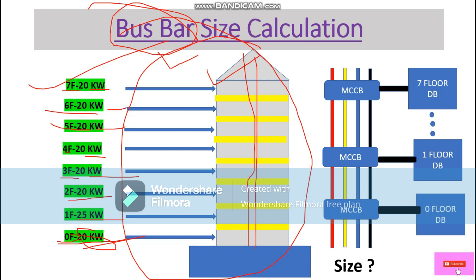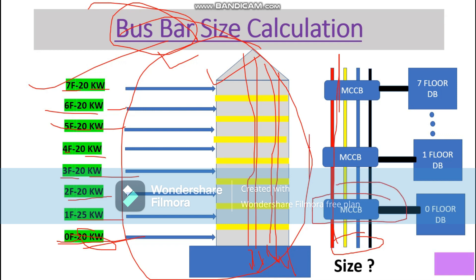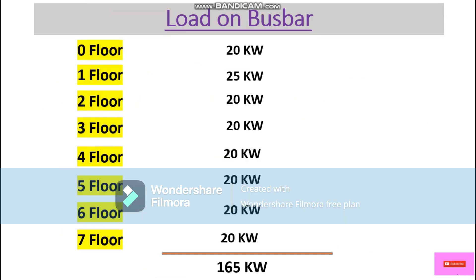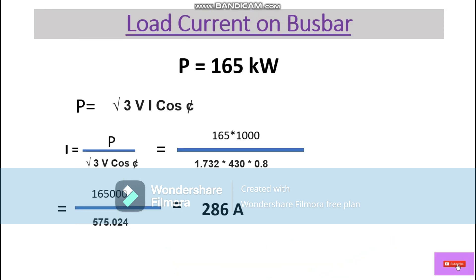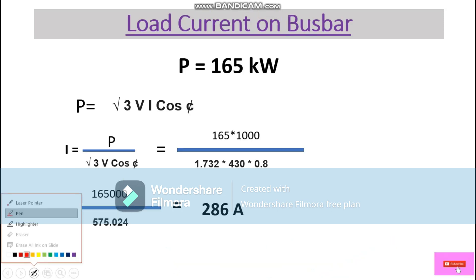The bus bar riser will be installed with four bus bars: R, Y, B, and one neutral. In each floor we have an MCCB or tap-off box to feed power to the floor panel. Now let's calculate the connected load. Summing all the floor loads gives us 165 kW as the total connected load on the bus bar.